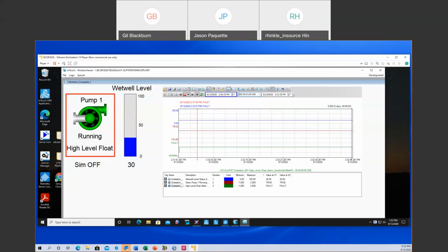I will tell you, there are many vendors. Allen Bradley, and I'm thinking lift stations right now. Allen Bradley has the MicroLogix 1400 that supports DNP3 natively, and we've worked with that. There's no additional cost for DNP3, it's just in there. If you're with the CompactLogix or ControlLogix, you have to put in a module to make that happen. And so there is a hardware cost to that. And again, in the case of SCADA packs, it's just natively in the unit.